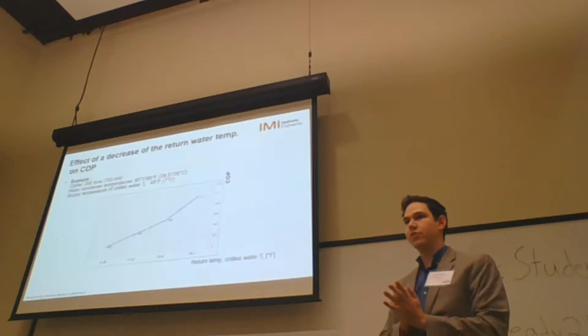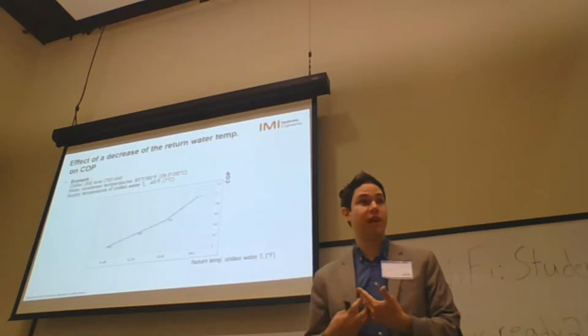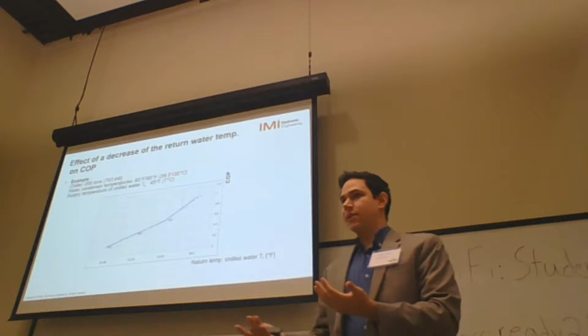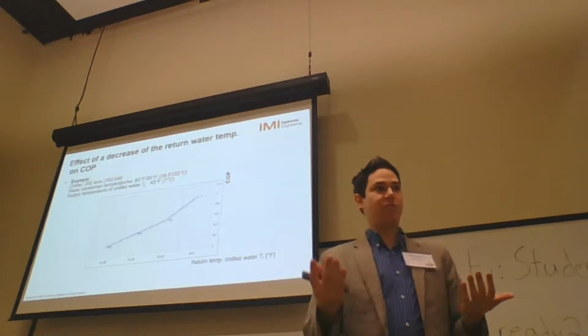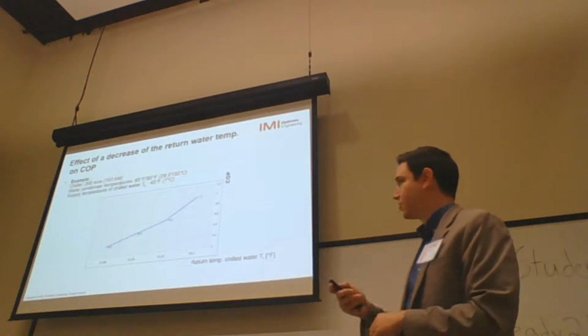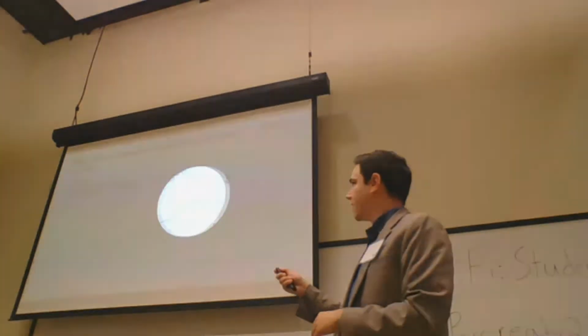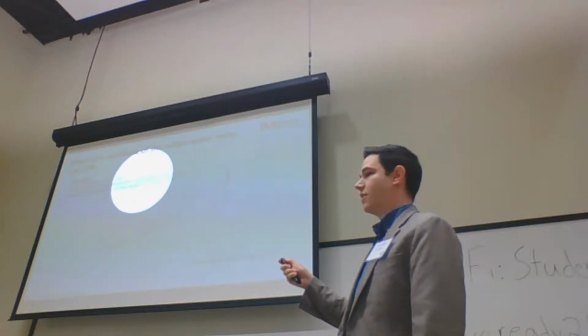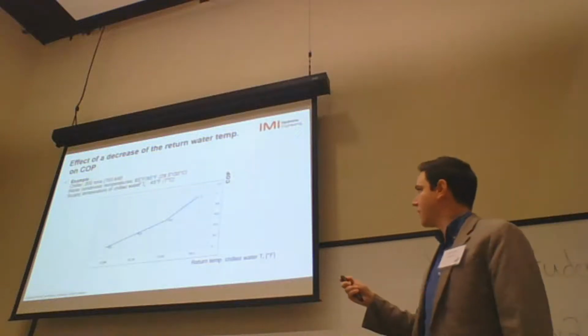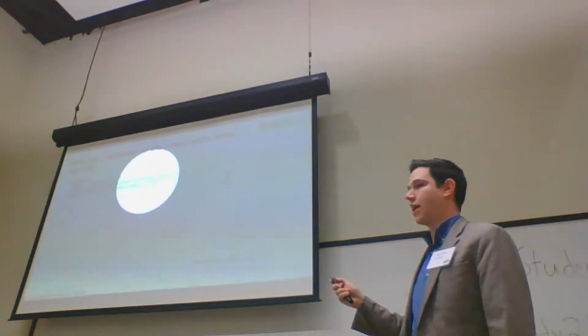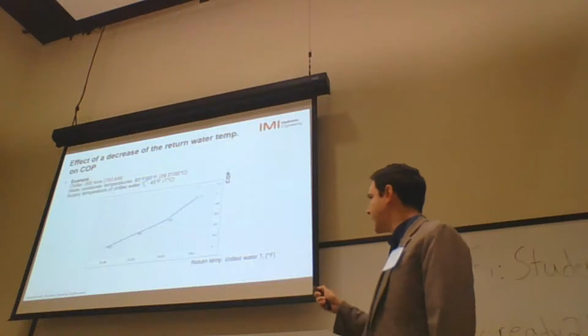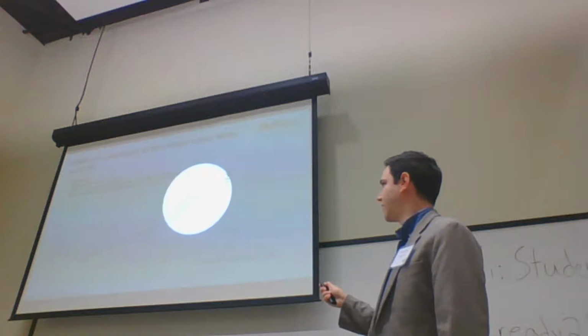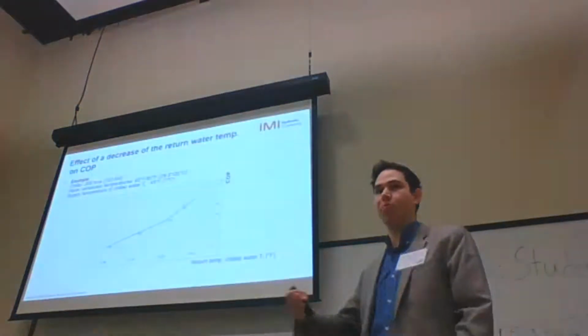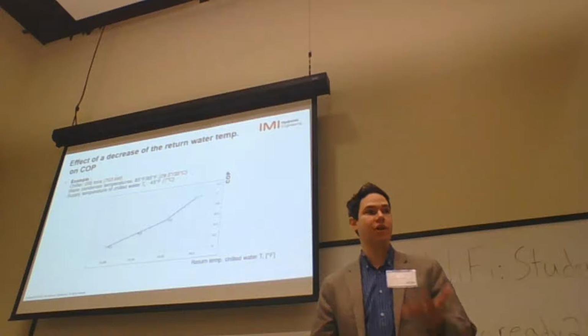So before we start talking about the low delta T issue, I'd like to first explain what is that. If you read some magazines, ASHRAE, NAB, you may hear about that before, the low delta T issue. Well, look at this example. We have a 200 tons capacity chiller, 10 degrees delta T in my condensing part, 85 to 95, and a 45 degrees supply to my system. If I do have my return temperature, chilled water, coming back at around the 55 degrees, I can achieve the COP, the coefficient of performance at my chiller of 5.